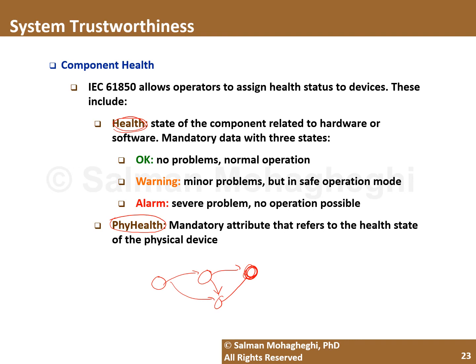So health is basically indicating the state of that component. It could be related to the hardware or the software of a particular component. And it has categories of OK, meaning that the component has no issues; warning, which is it has some minor problems but it's still operating in the safe mode; or alarm, which is the component has severe problems and is not operational. Likewise, we can have physical health, which is kind of the same concept, except that it refers to the physical aspect of the device.